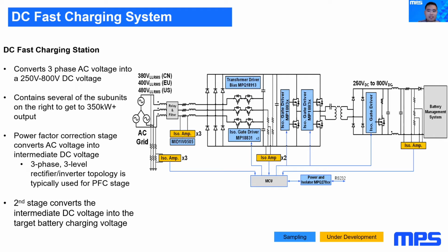A DC fast charging station typically contains several of these subunits, which generally range from 30 kilowatts up to 75 kilowatts. Multiple subunits are put in parallel to achieve 250 kilowatts, 350 kilowatts, or even higher amounts of power. The DC fast charging system is generally comprised of two conversion stages.